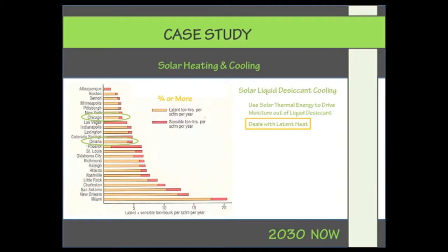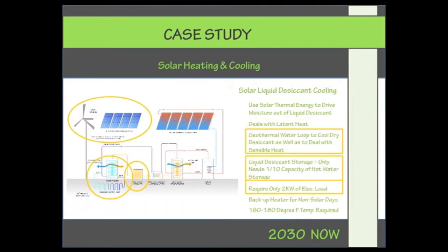So basically, this deals with latent heat, which is the humidity portion of the cooling load. And in the Midwest, I don't have Iowa, but like Chicago, Omaha, more than three-quarters of the cooling load is from latent heat. So dealing with the latent heat or humidity is the best way for cooling efficiently. So again, this is a liquid desiccant system.